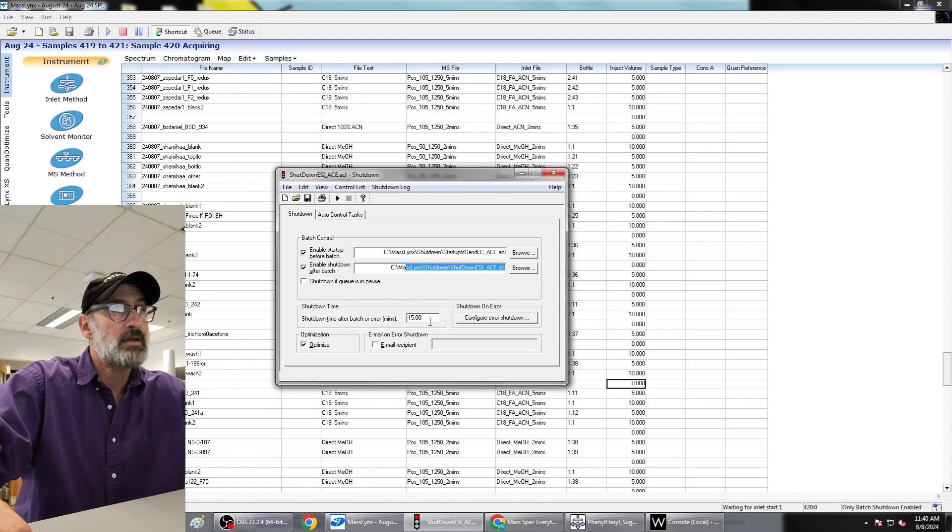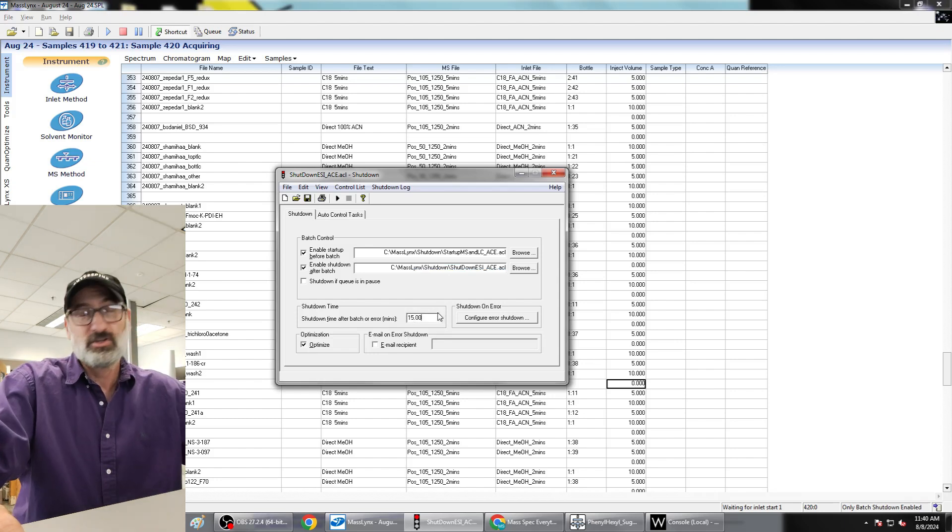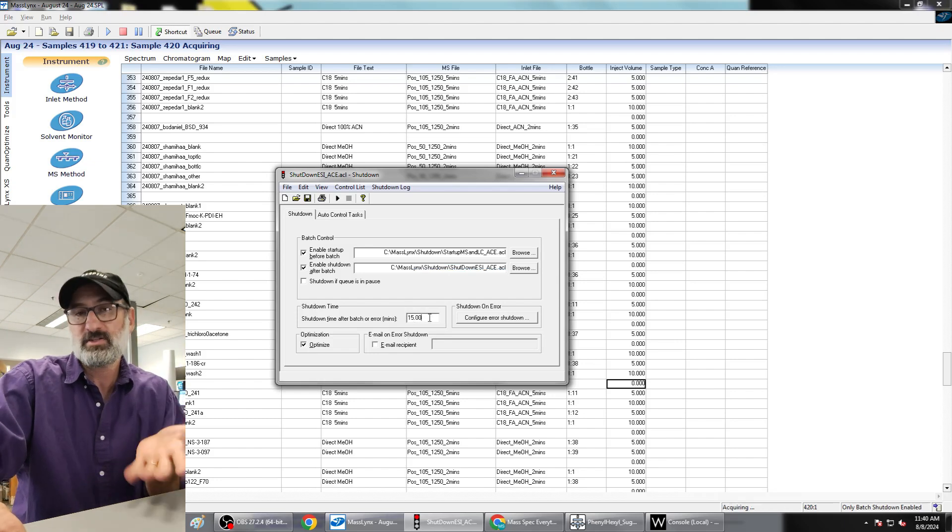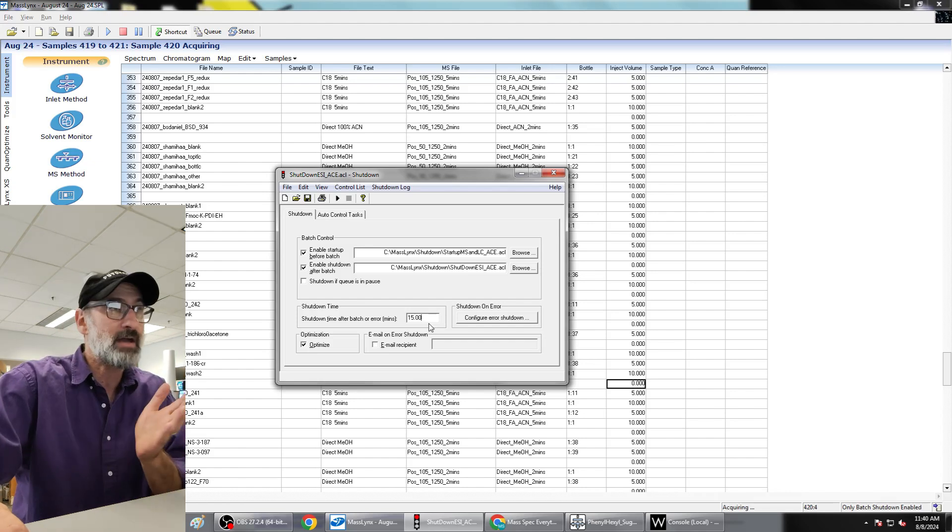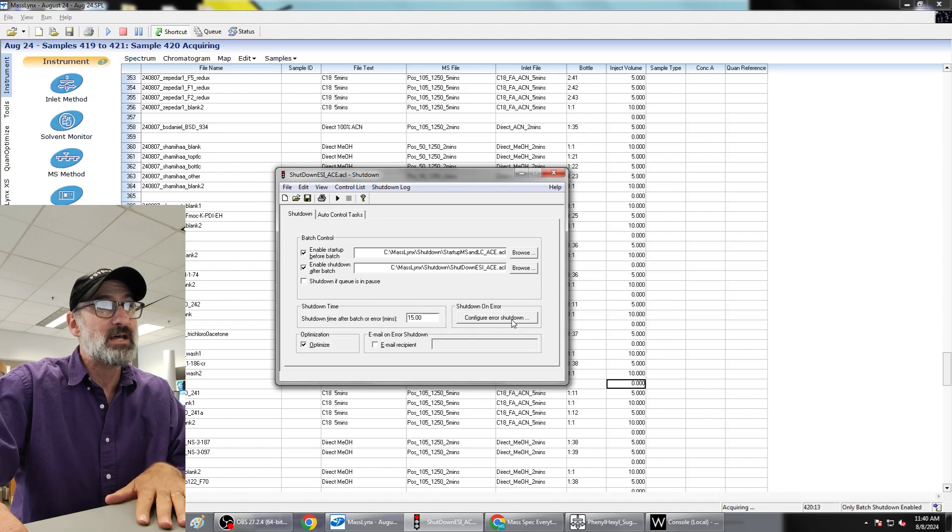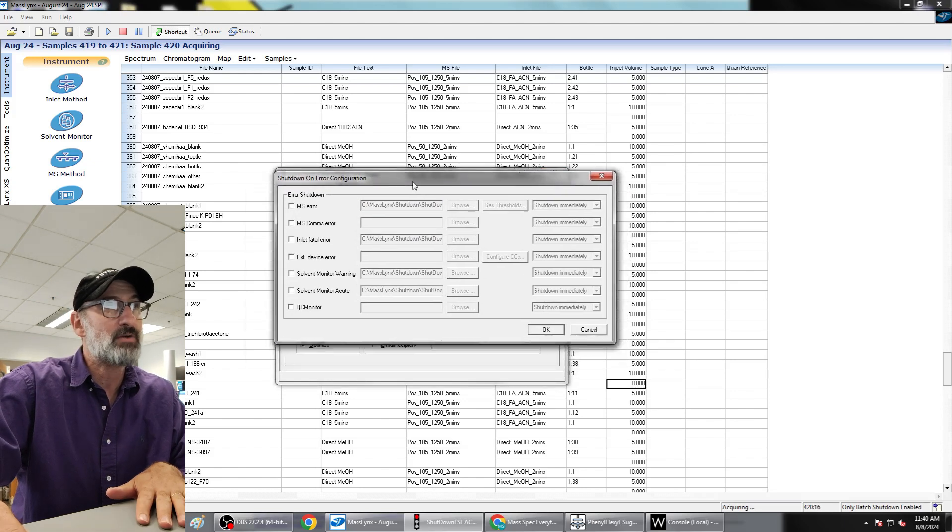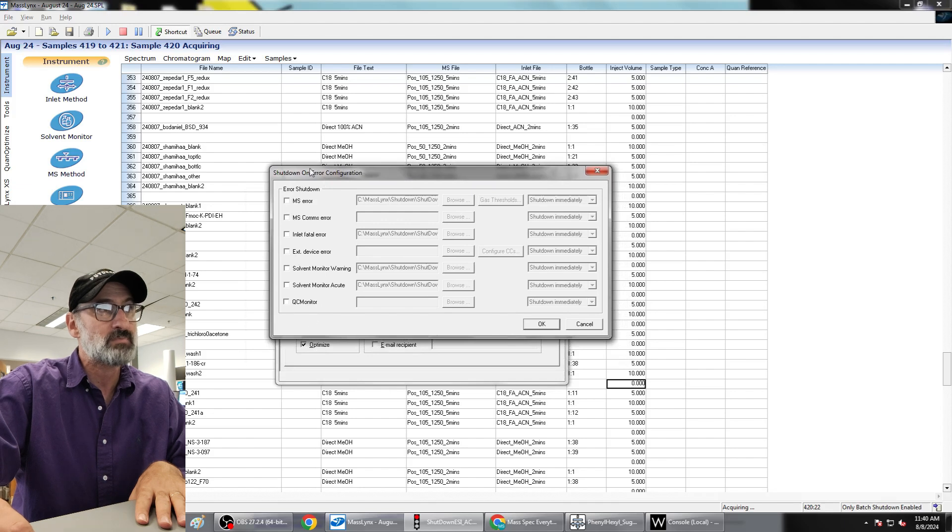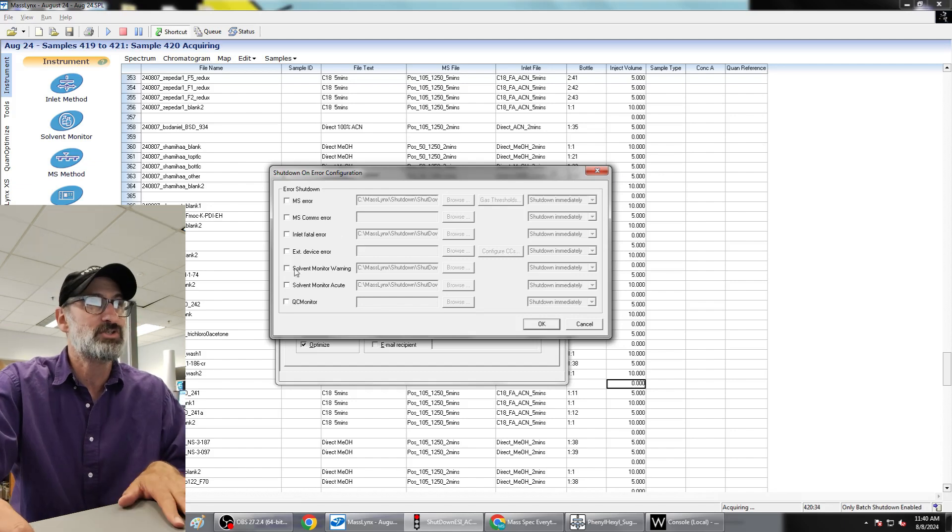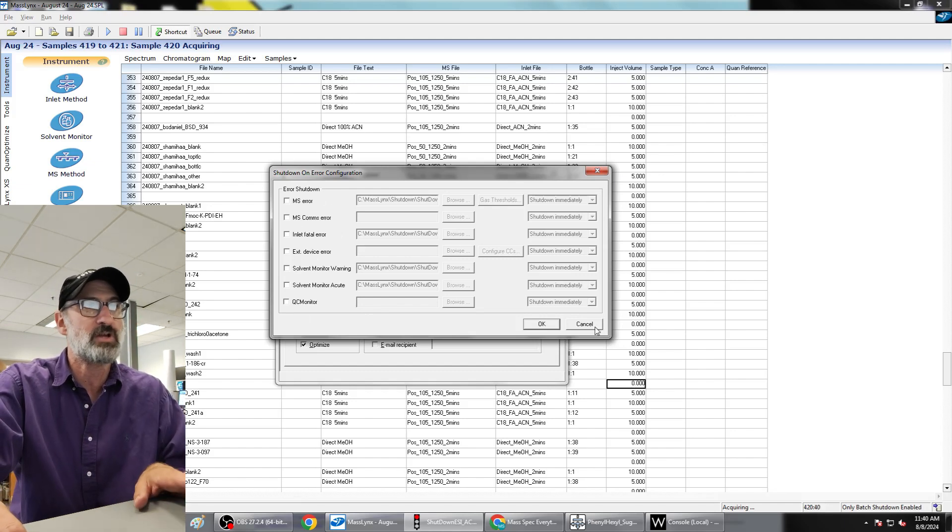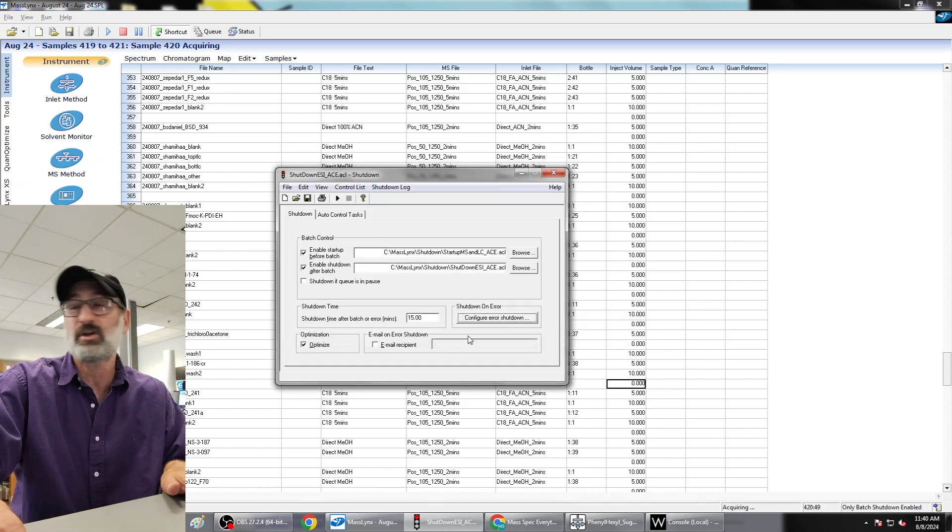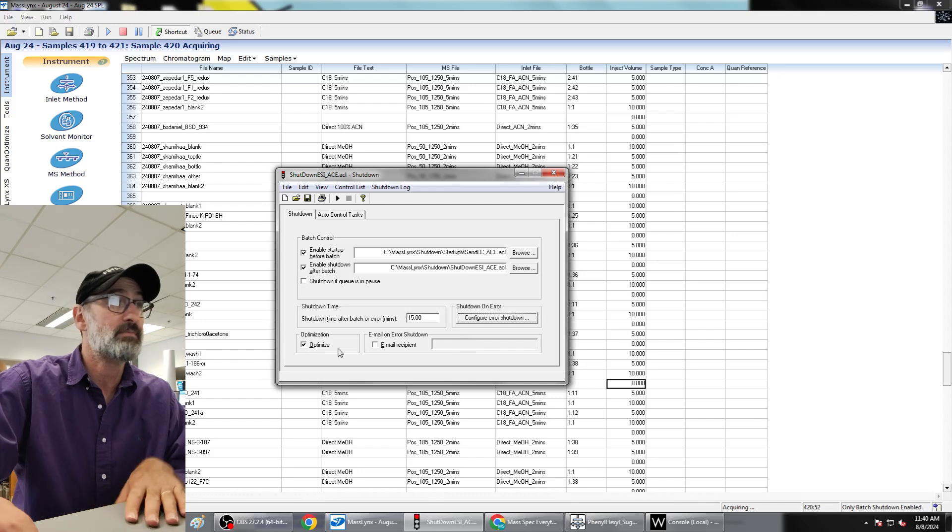And after a run, you want it to wait 15 minutes so you're not turning the thing off and on again. You have 15 or 20 minutes or 30 minutes or the whole class, it doesn't matter, until the instrument turns itself off automatically. And I also like to get rid of all the configure error on shutdown things, so I just let the system turn itself off after 15 minutes. You can make it turn off immediately if there's another error, but I don't do that. I'm going to be around so I figure I can address the errors the instrument's doing.